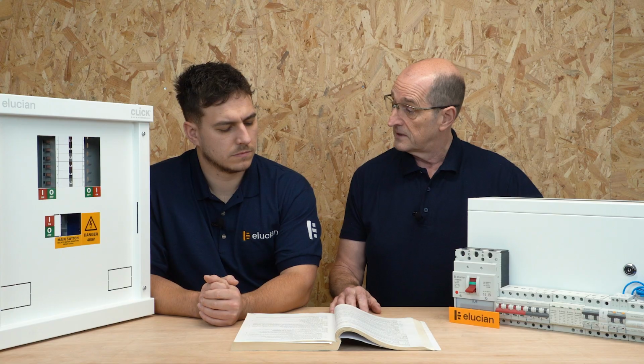What changes with each of them is their ability to manage levels of DC current that naturally exist because of the electronics that's connected, and the levels of frequency that perhaps might exist, particularly when you're dealing with frequency motors and things like that, such that the frequency is different to the 50 hertz that we normally have.